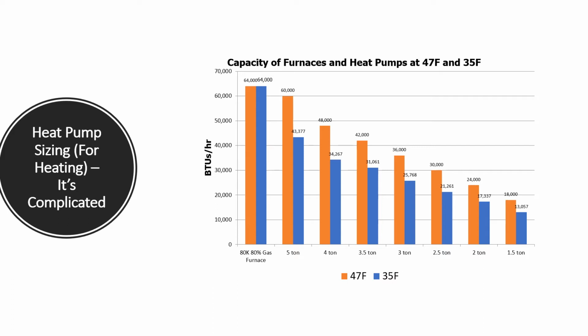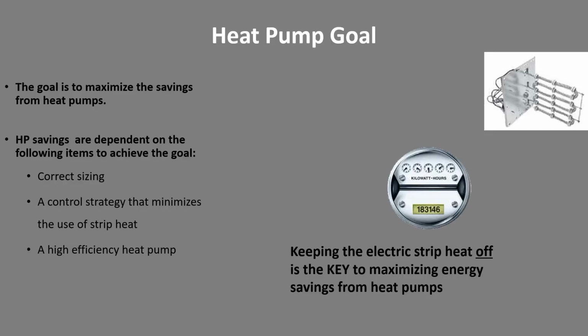Let's look at a 2-ton unit over here. Sure enough, at 47 degrees, it's 24K. But by the time you get to 35, really you have a 1.5-ton machine.